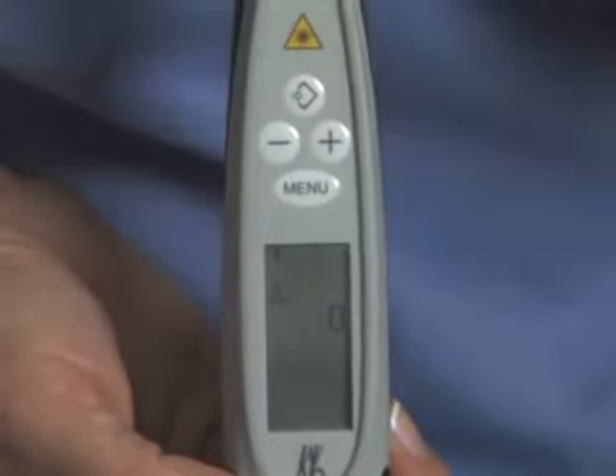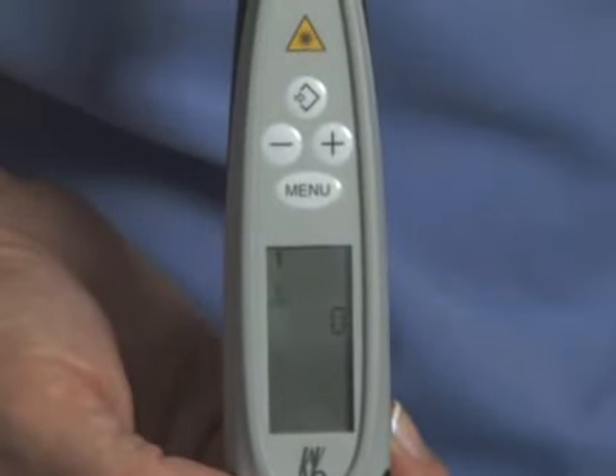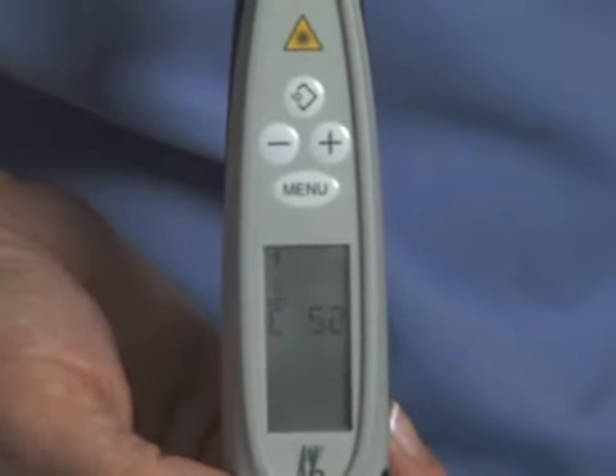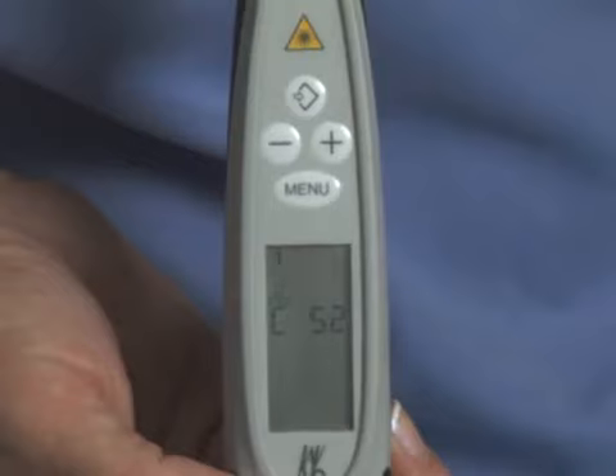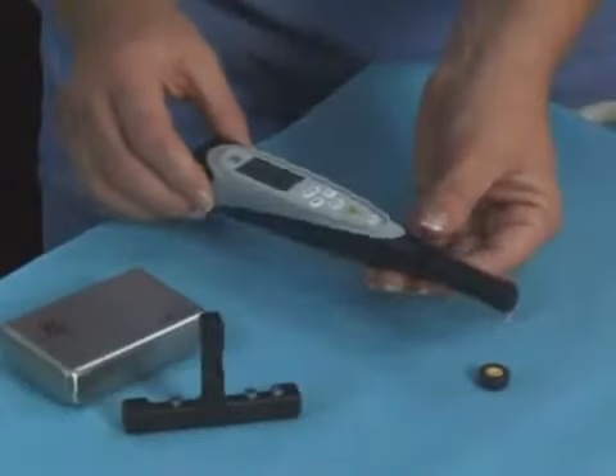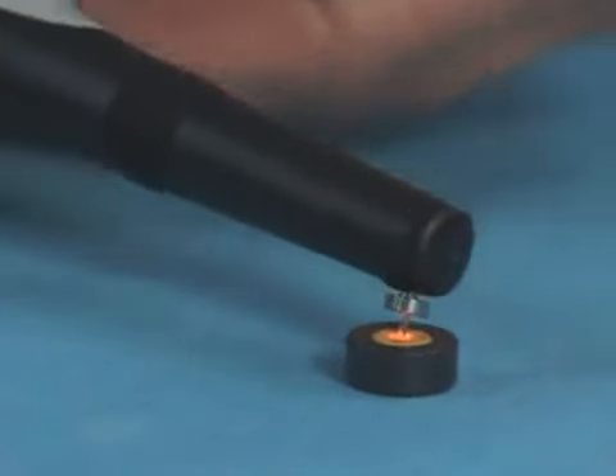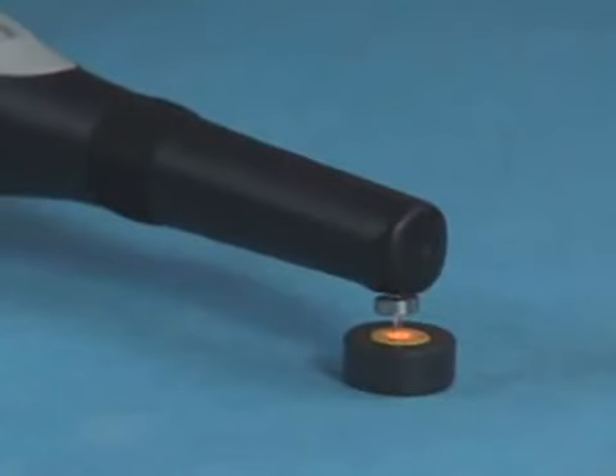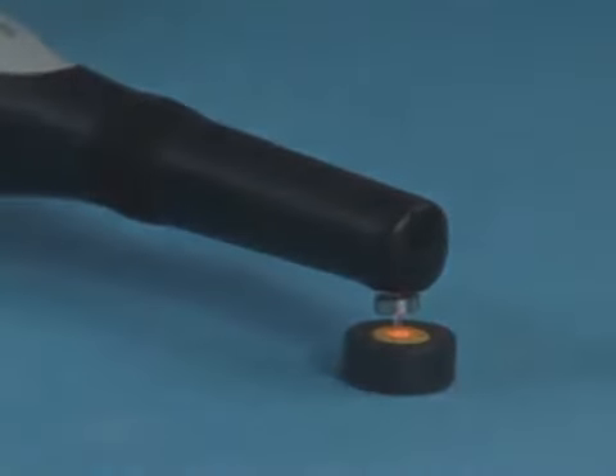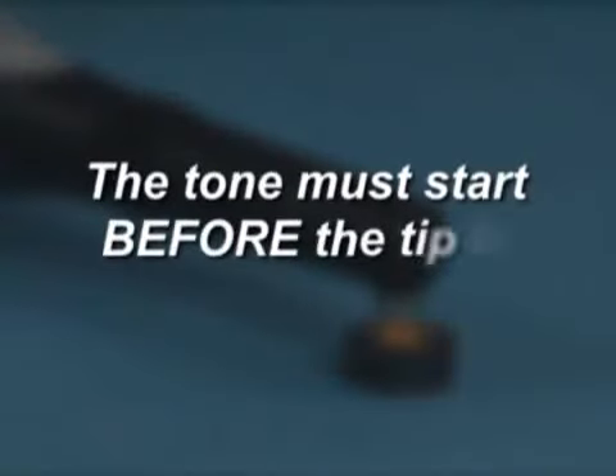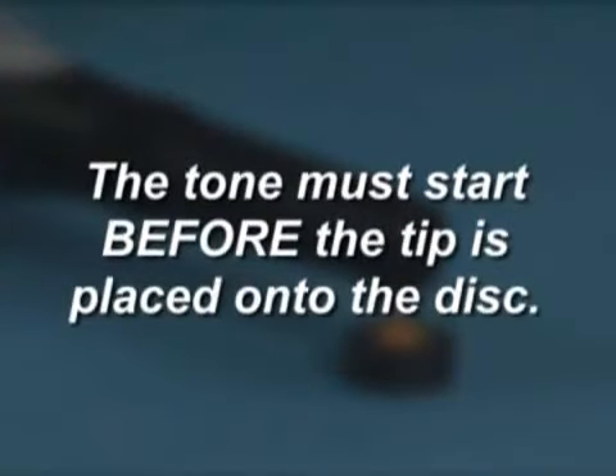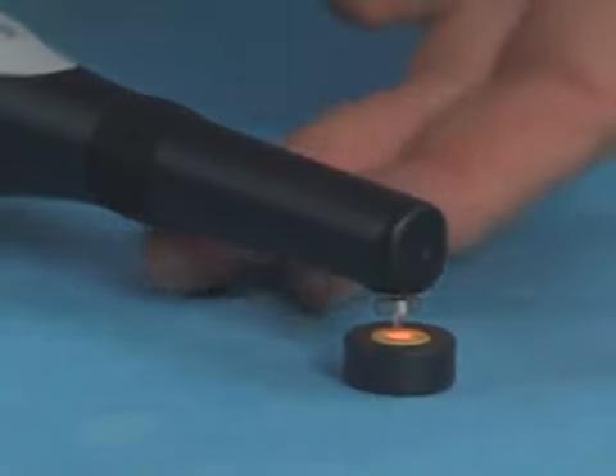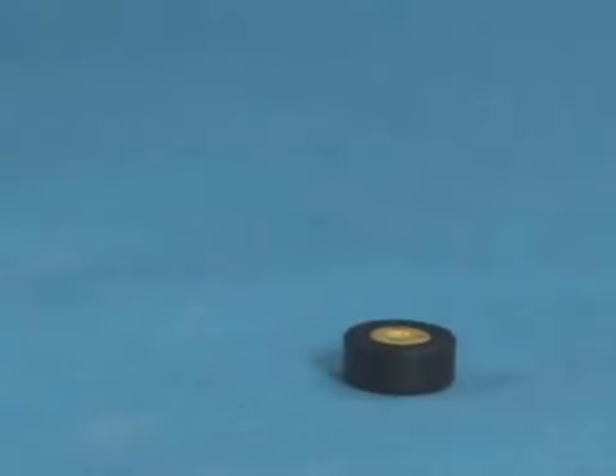by the Enter button. A small 0 will appear in the display followed by a large 0. The display then changes to a letter and a 2-digit number, and the unit will emit an audible tone. When the audible tone begins, gently place the tip on the calibration disc at a 90-degree angle, holding steady. Please note, the tone must start before the tip is placed onto the disc. When the tone stops, calibration is complete and the unit is ready to use.